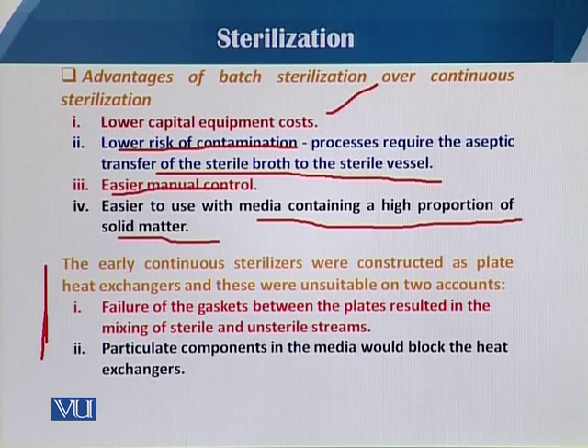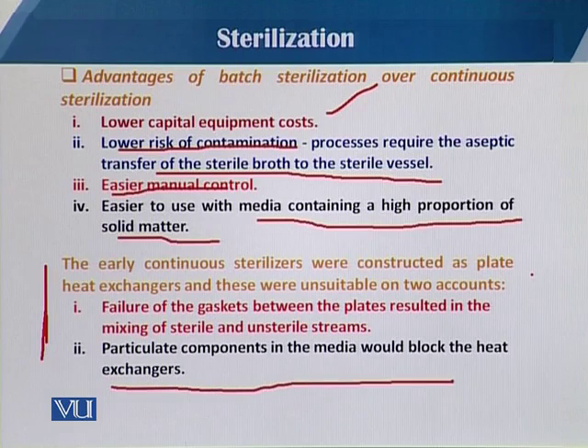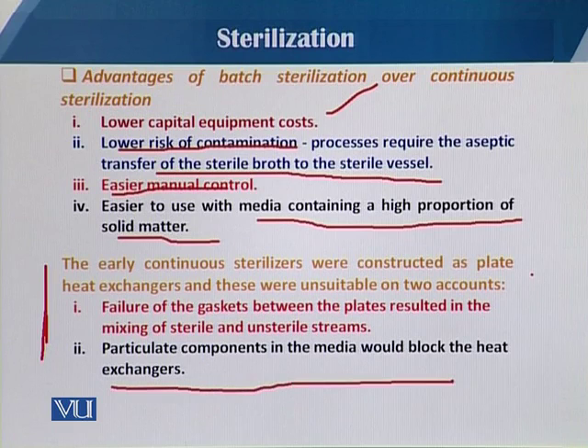Early continuous sterilizers were constructed as plate heat exchangers, but these were unsuitable for two reasons. First, failure of the gasket between the plates resulted in mixing of sterile and unsterile streams — if there is leakage between plates, sterilized and unsterilized medium can mix. Second, particulate components in the medium would block the heat exchangers due to the very small passages, especially with viscous media.